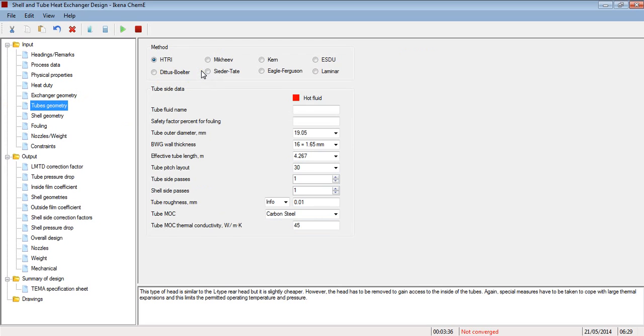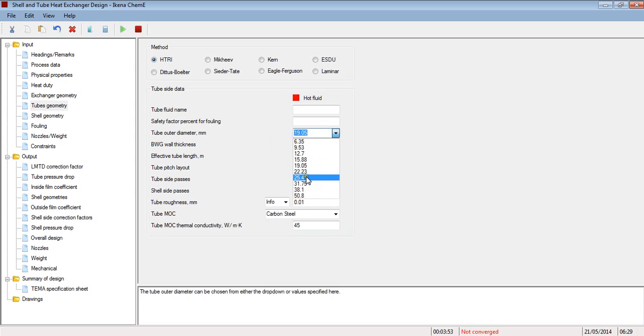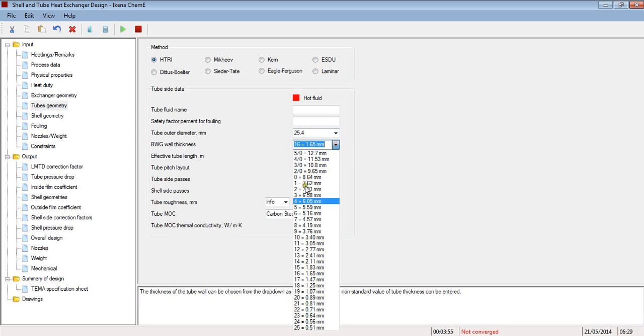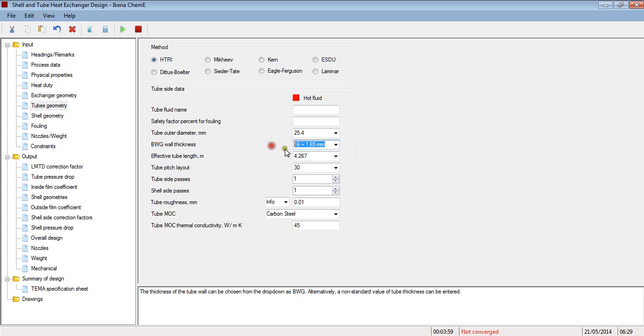Here you can set the tube heat transfer coefficient calculation methods. The program defaults to a correlation recommended by HTRI, but you can choose any of these. And some of the most important tube side data can be entered here. I will use 1-inch tubes. You can use one of these standard thicknesses, but I will go ahead and enter a value, let's say 2 mm.